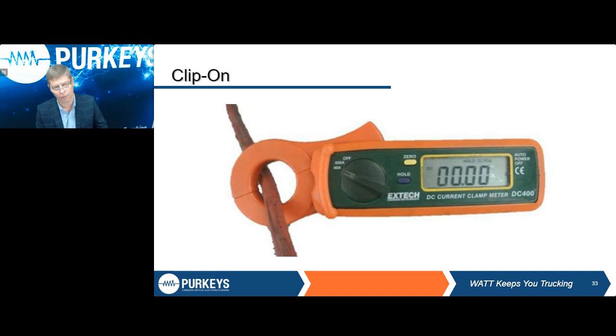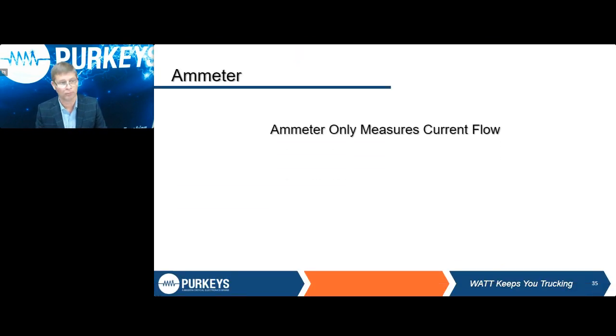Again, it's either going to have an arrow molded into the jaws, or it's going to have a sticker in there to tell you the direction of current flow. You got to make sure you are looking at the right one. But what does an ammeter do? Simply measures current flow. In order to have current flow, though, what do you have to have? You got to have voltage pushing it. If you don't have any voltage, you can't have any current flow either.